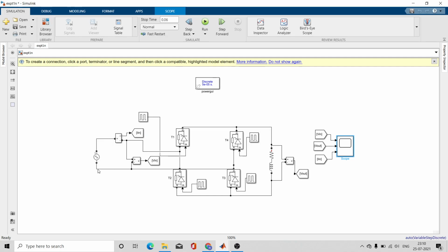When you are studying an inverter, where you convert DC into AC, at that point you will see the harmonic current at the output side or load side of the inverter. Remember, for a rectifier you see the harmonic current at the source side, and for an inverter you see the harmonic current at the load side.